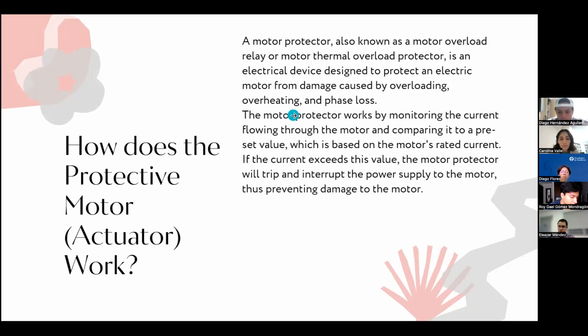The motor protector typically consists of a current sensing device, a thermal sensing element, and a relay. The current sensing device, such as a current transformer, measures the current flowing through the motor and sends a signal to the relay. The thermal sensing element, usually a bimetal strip or a thermistor, measures the temperature of the motor and sends a signal to the relay when the temperature exceeds a preset limit.